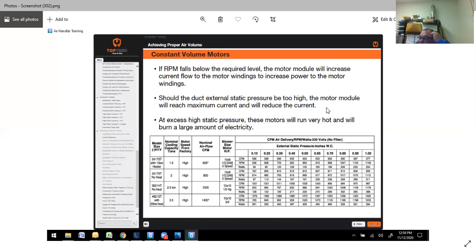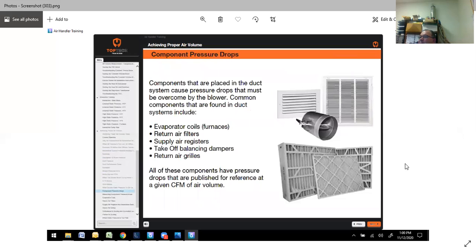That much difference. And even though you're running at 9 amps and that motor's working triple time, you're not getting nearly the airflow you should. In fact, you're basically burning up the system. At that point, customers will complain because they're going to be super, super loud, and chances are they're not going to be comfortable. It will affect the comfort of the home.